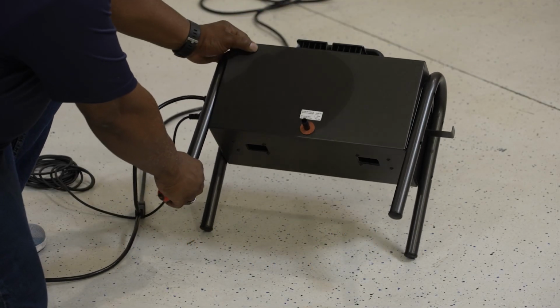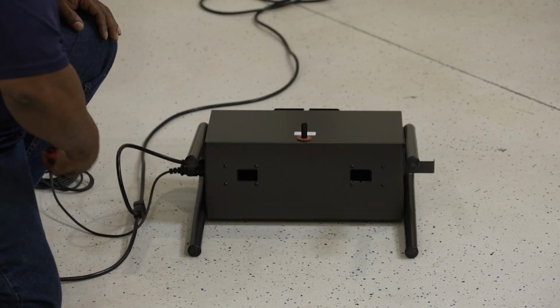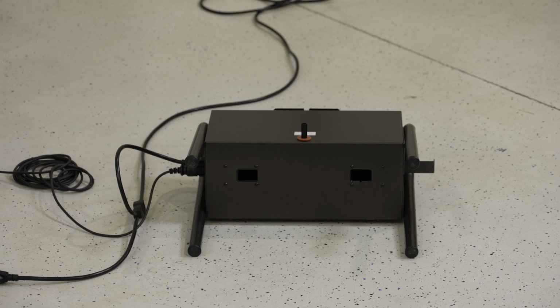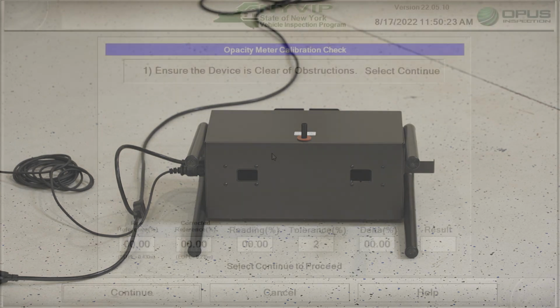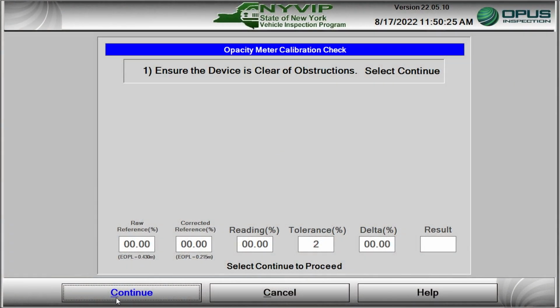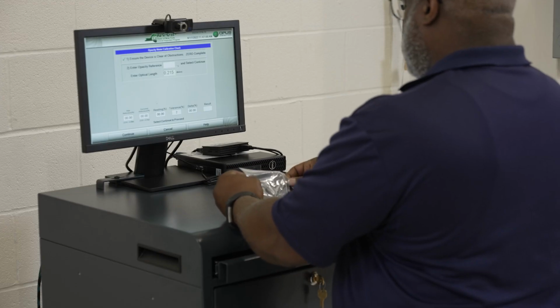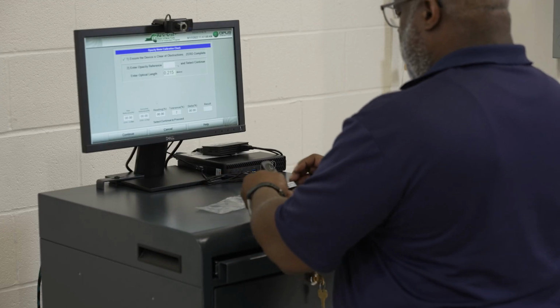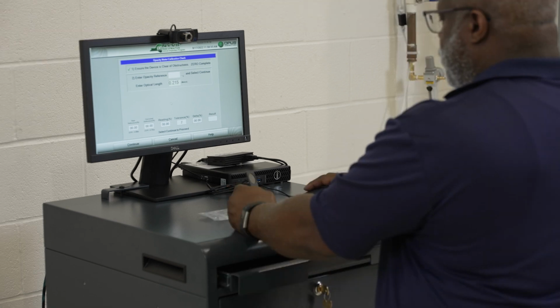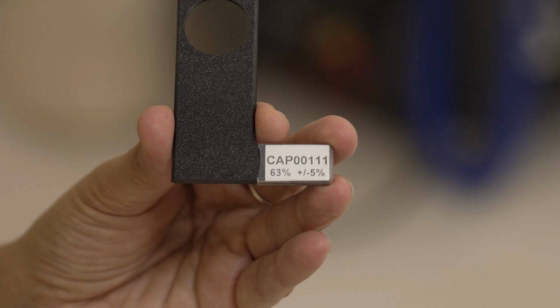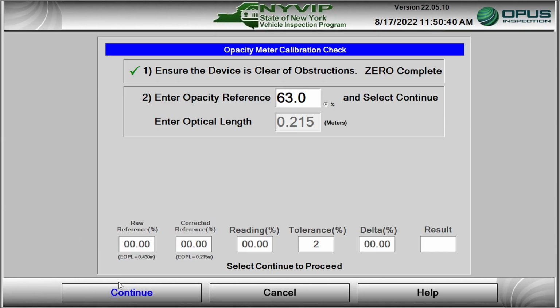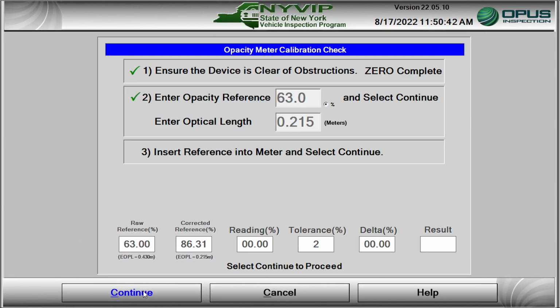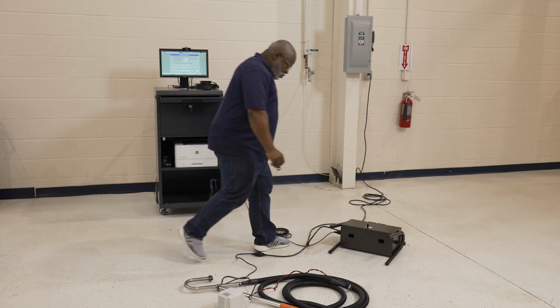To begin calibration of the opacity meter, make sure the opacity meter is clear from obstructions. Lay the meter on its side. Click the Continue button to zero the meter. Locate the calibration glass. Carefully remove the glass from its protective sleeve and enter the reference opacity percentage into the dialog box. In this case, the reference is 63%. Click the Continue button to proceed.